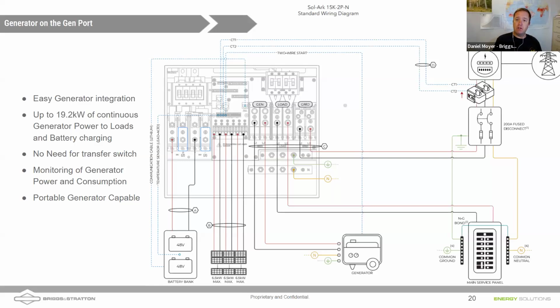In this example, we've got our grid coming in up on the top right through our meter, there's our disconnect. We always recommend installing those CTs, even though the Sol-Ark has built-in CTs -- those give you a little extra redundancy and performance. Bring it in on the grid port, 200 amps in, 200 amps right back out to that load center you see down there. Then we have the generator -- although it looks like a portable generator, that's really a standby generator. We're using a 2-wire signal to start up that generator based on the state of charge of the battery, which can be adjusted in the Sol-Ark.